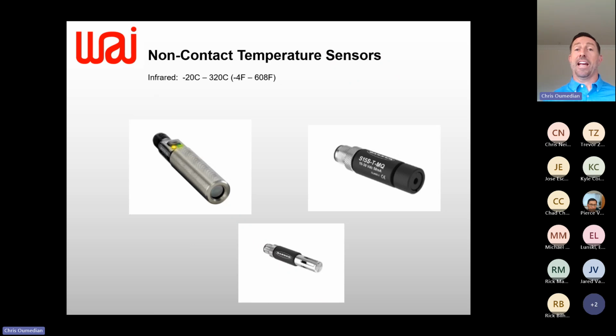So think, a tank with hot water or some hot media in it, or a motor or a device that you want to measure what's going on. You want to measure temperature runaway on a gearbox, something of that matter. You would use something like one of these devices on the top, and the range is a little bit smaller than the RTDs or thermocouples, but they still cover a pretty good range. Negative 20C to 320C, which equates to negative 4F to 608 degrees F is your range. So call it 0 to 600 degrees Fahrenheit we can measure with these non-contact devices. They are non-contact, but infrared is a light source that measures heat. So you can imagine your limitation is going to be range.